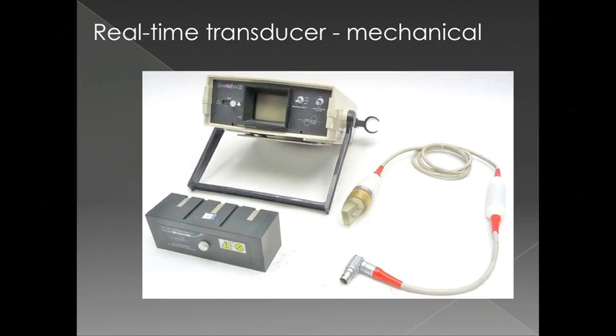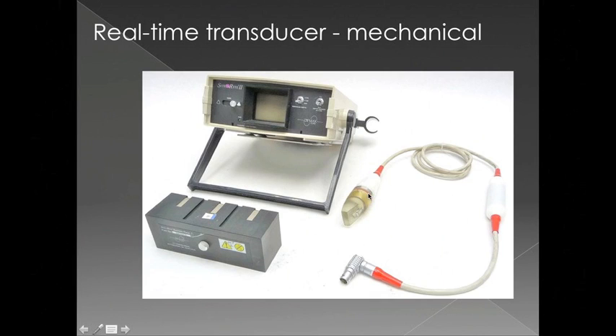This is a picture of one of those mechanical transducers. You might still see these in some of the smaller vascular access devices, like a Site-Rite or some older Sonosite devices, where you actually still have that little stick with the transducer element wiggling back and forth on it.